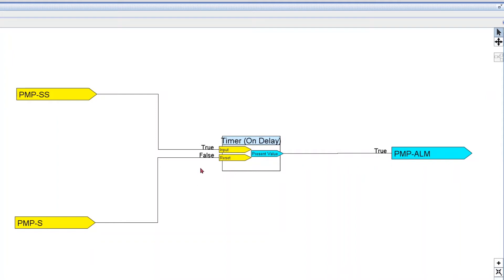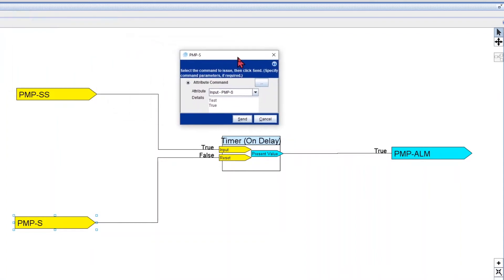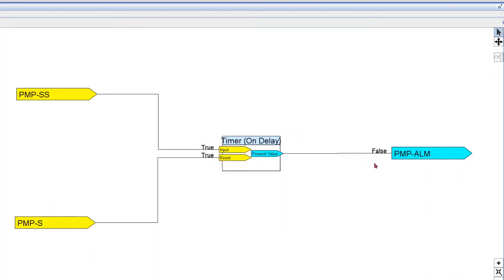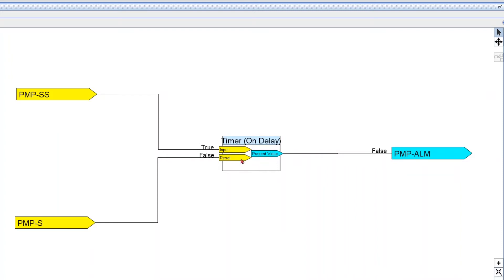Now the second part: every time you put a true to the reset, it's gonna force the output to false. So if we get a status from the pump — let's command it to true — it's gonna force the output to false, meaning the alarm goes away. Now let's say we lose our status. If we put a false to the reset, the timer is gonna start counting again before it can output a true. So I'm just gonna command status to false, meaning we lose our status. After 15 seconds without status, we get the alarm.